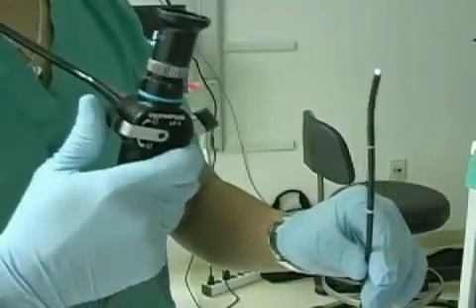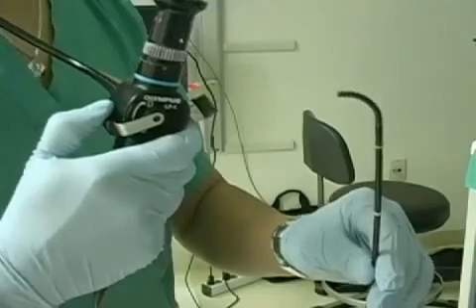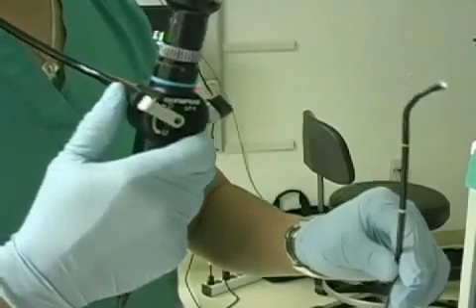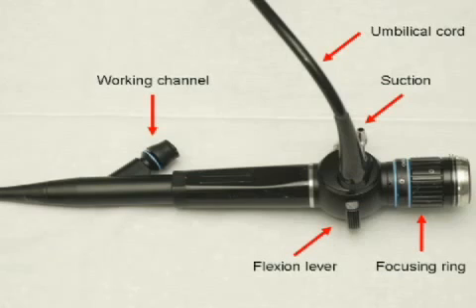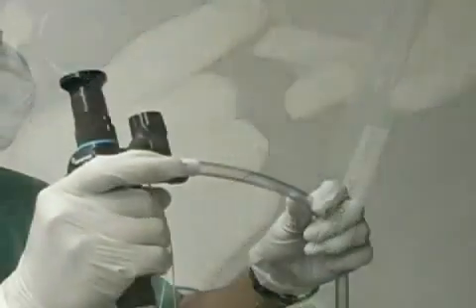The handle of the bronchoscope is fitted with a lever, which controls flexion and extension of the tip of the bronchoscope in a single plane. The handle also contains the proximal port of the working channel, which extends distally to the tip of the scope. This channel can be used to pass various instruments into the airway, and can be used for irrigation, administration of medications, and suction.